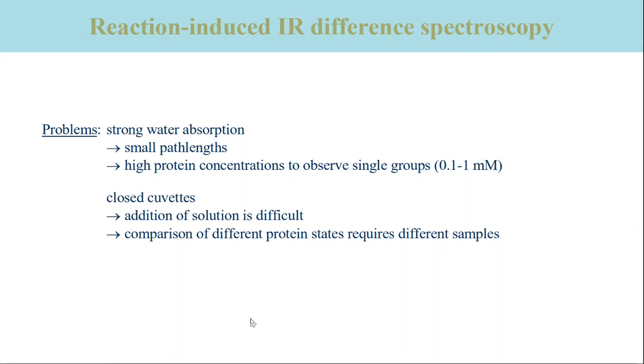A problem of infrared spectroscopy is the strong absorption of water in an interesting spectral region, which is the amide 1 range around 1640 reciprocal centimeters. This requires short path lengths in H2O of less than 10 micrometers and in D2O of 50 micrometers.